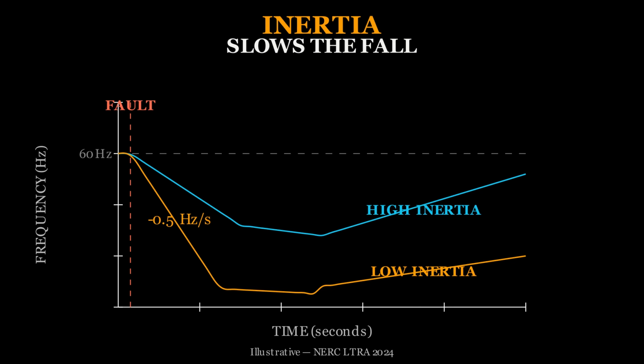Here's why. Generators have protective relays. Those relays watch for abnormal conditions, including fast frequency changes. If frequency is changing too fast, the relay assumes the generator has lost its connection to the main grid. It assumes the generator is running uncontrolled, alone, in an island. So it trips the unit offline. This is called a nuisance trip. In a low inertia system, an event causes fast ROCOF, which causes nuisance trips on other generators, which removes more generation, which accelerates the frequency drop, which triggers more trips.